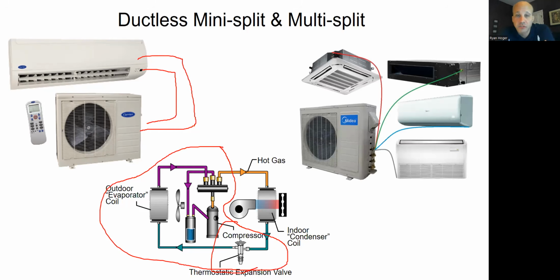There's also multi-split systems. So what this is, it's one outdoor mini split system that is feeding not just one indoor unit, but 2, 3, 4, 5 indoor units. In this case, each one of them has 2 refrigerant pipes going back to the unit. So there's 1, 2, 3, 4 ports on this guy. This drawing's bad. It should actually show them going to each of these ports. But there's a pair of ports going to each indoor unit. So in this case, it works the same way. The outdoor unit's a heat pump, so it can either be a condenser or an evaporator. The indoor units can either be a condenser or evaporator coil.